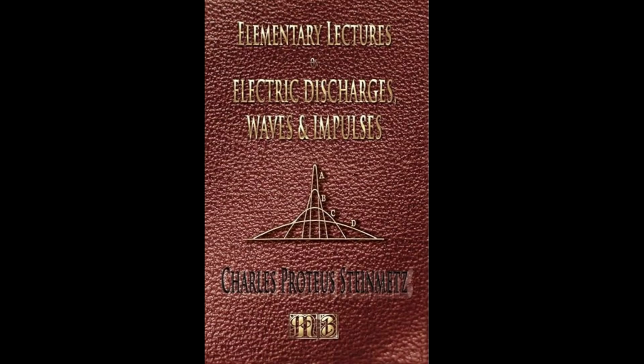With a single-phase short circuit on a polyphase machine, the double-frequency pulsation of the field resulting from the single-phase armature reaction induces in the machine phase, which is in quadrature to the short-circuited phase, an EMF which contains the frequencies f, 2f plus or minus f, that is, full frequency and triple frequency. And as the result an increase of voltage and a distortion of the quadrature phase occurs, as shown in the oscillogram, Figure 25. Various momentary short-circuit phenomena are illustrated by the oscillograms Figures 26 to 28.